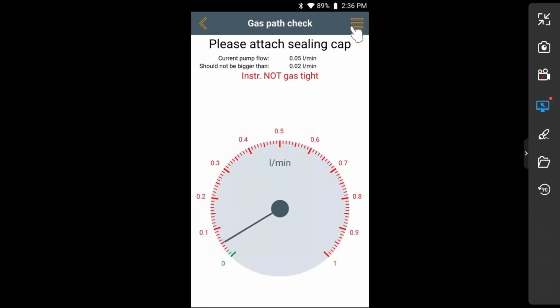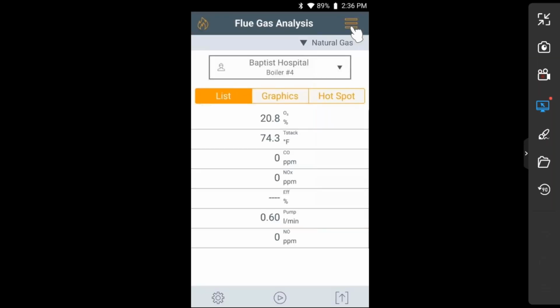And that vacuum needs to go down to zero, almost zero, before it passes the test. Right now, it's telling me it's tight, which means that my water trap is closed. I have no leaks in the hoses. My filter and the top of my probe handle are locked in place, so I can do a test and not have to worry about any type of dilution from outside air. It's a very nice test that you have access to in the analyzer.